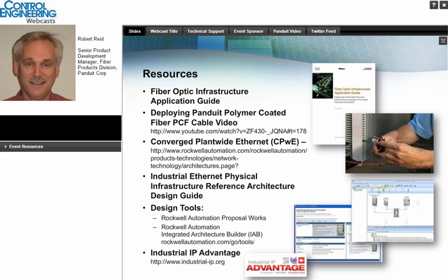As far as reliability, one versus the other, I would say that the SC connector is probably the most robust of the three. The ST is not; you can pull on the tail of the connector and demount it. Both the LC and the SC are what they call non-optical disconnect. So when you pull on the cable, you don't demate the connector.